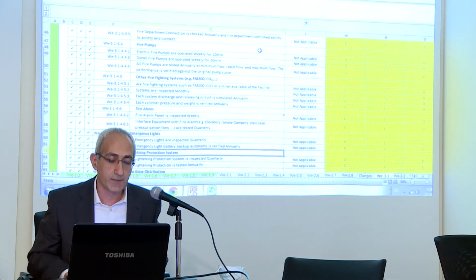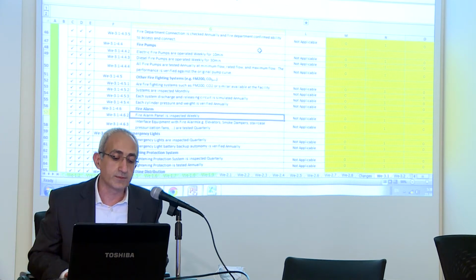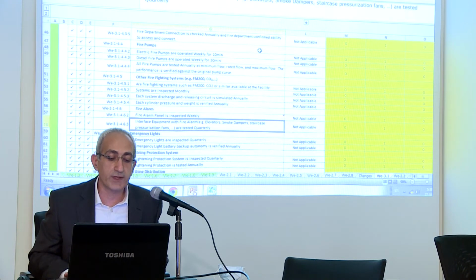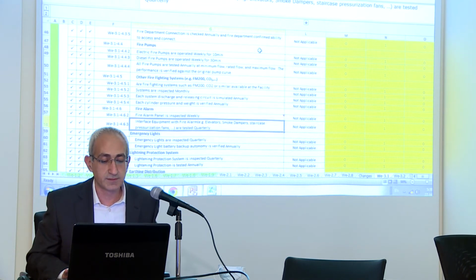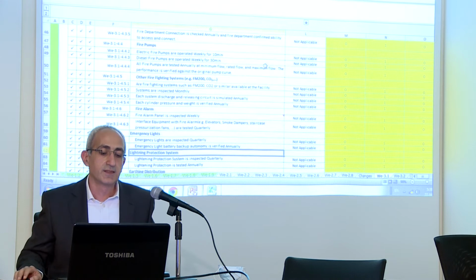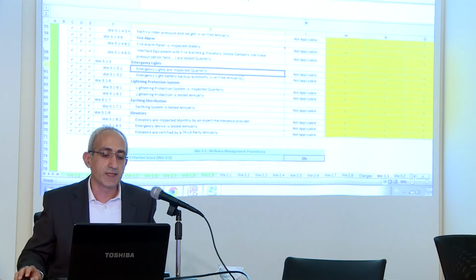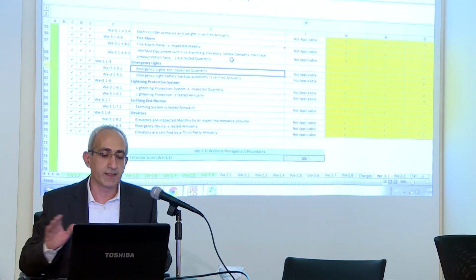Fire alarm. The panel is inspected weekly for alarms and troubles. Interface equipment with the fire alarm is tested quarterly. So you have to test your fire dampers, operable windows, closable fire doors, elevator recall, staircase pressurization, and what have you, quarterly. Basically, installed emergency systems need to be tested between weekly and quarterly.